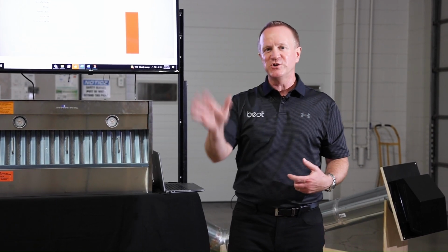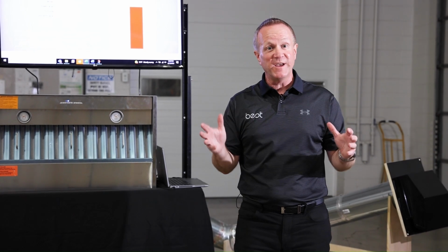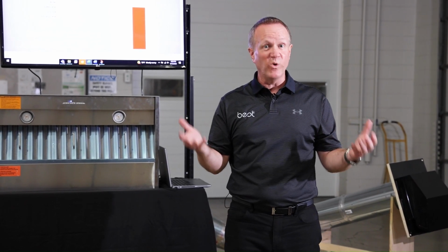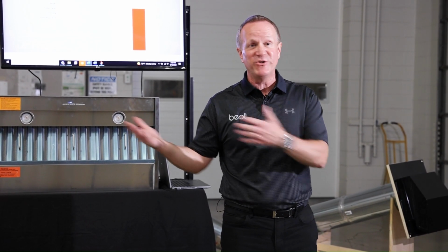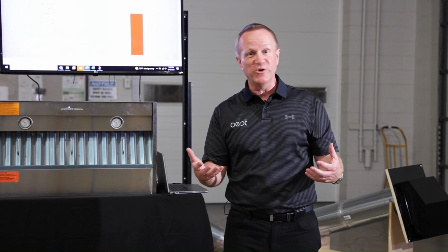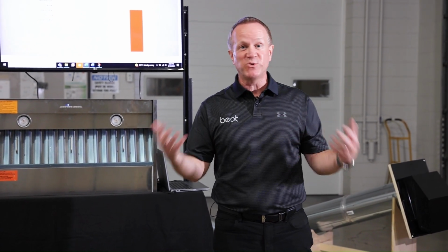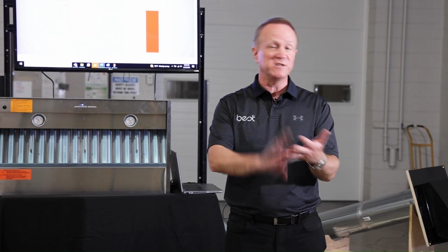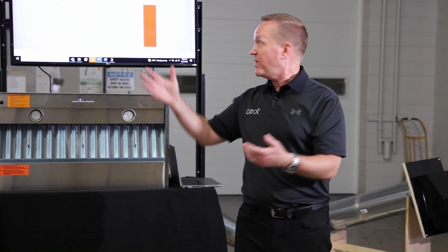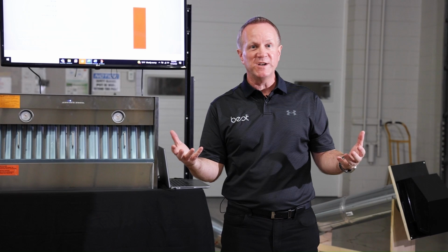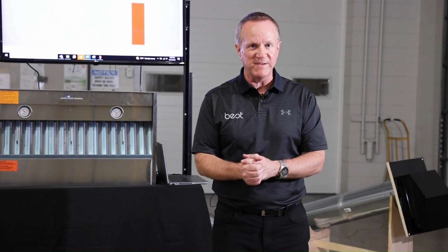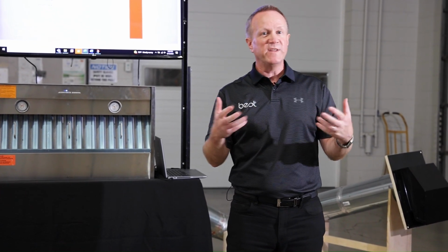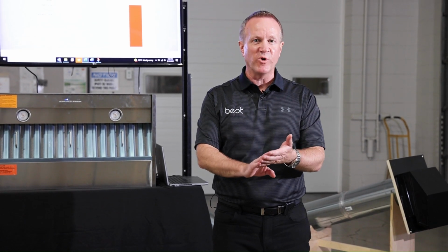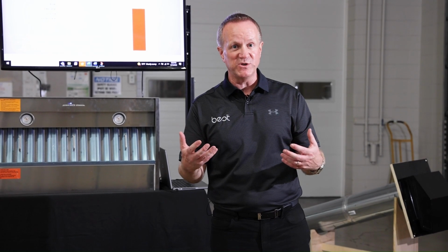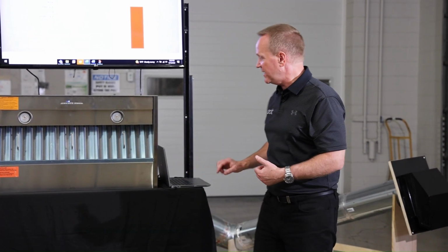So I can already understand what everybody is thinking. You're thinking to yourself, this is literally the worst demonstration I've ever seen anybody do. You tell me that 600 means 600, 1200 means 1200 with Best because of IQ, because of the Guaranteed Performance System, but you hook it up and you show that it's 530, 535 CFM. Well, the one thing that we've talked a lot about in the Guaranteed Performance System is the calibration. The thing we haven't done yet with this hood is we haven't calibrated it yet.